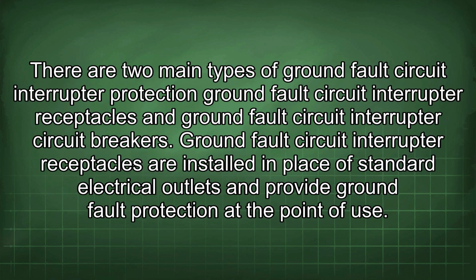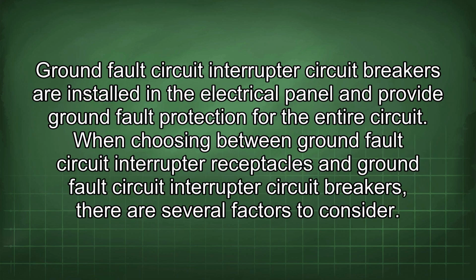There are two main types of ground fault circuit interrupter protection: ground fault circuit interrupter receptacles and ground fault circuit interrupter circuit breakers. Ground fault circuit interrupter receptacles are installed in place of standard electrical outlets and provide ground fault protection at the point of use. Ground fault circuit interrupter circuit breakers are installed in the electrical panel and provide ground fault protection for the entire circuit. When choosing between ground fault circuit interrupter receptacles and ground fault circuit interrupter circuit breakers, there are several factors to consider.